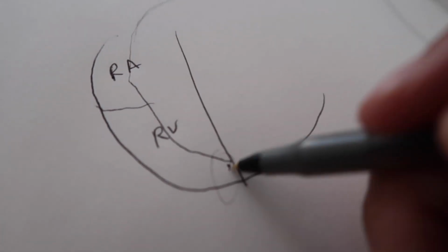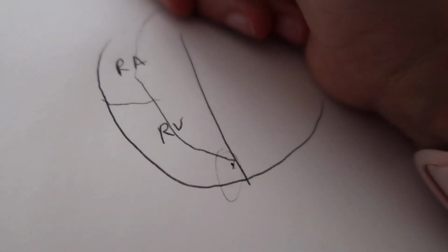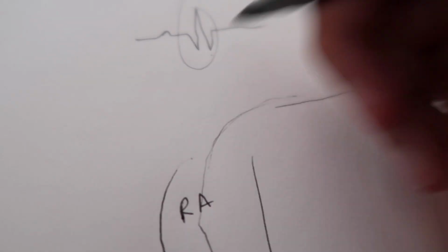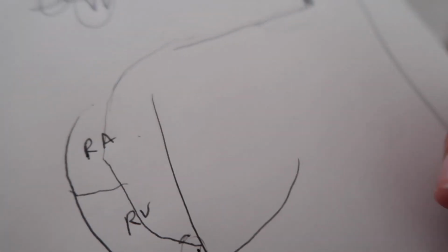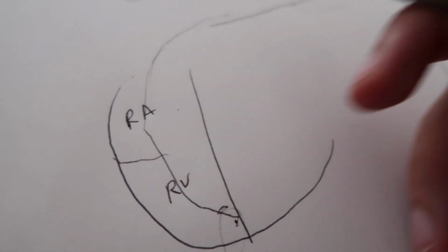All right. From these clips, I can test the area in the heart where the lead is. I can map the area, measure the QRS. We want to measure the QRS when we're in the ventricle, and we want to measure the P wave when we're in the atrium, and that is basically an electrical signal that we want to make sure we see appropriately. We also measure the impedance, which is the electrical resistance of the wire. This confirms whether we have good contact with the cardiac muscle, and we also want to make sure it's stable. So we take multiple measurements, and that also tests the integrity of the wire and of the lead.